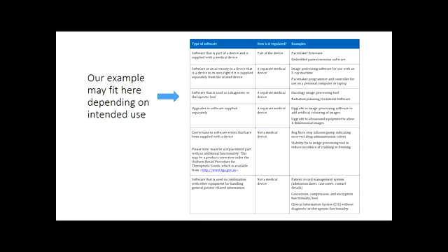So if it's an accessory to a device that is a device in its own right, and it's supplied separately, then it's a separate medical device, right? If you have to buy it separately and then put it together. If you're selling it as a kit or a system, then it's not. So I think that our example would be software that is used as a diagnostic or a therapeutic tool. The Connect example that we used, so it would be a separate medical device.